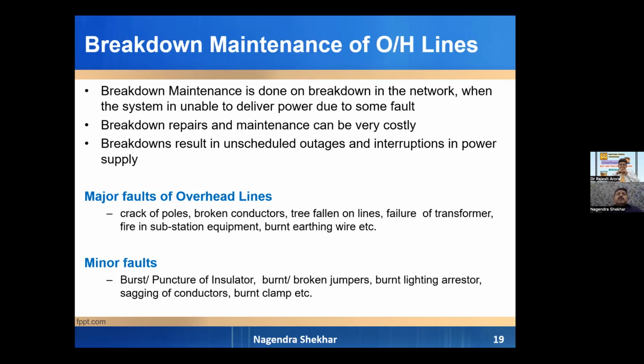Breakdown maintenance. Breakdown, as I told you, is when a system or network stops working, so we fail to deliver power supply to our consumers because of a fault. This fault can happen at any stage, because all equipment is connected in series, so a fault at any stage results in power failure in the area. When power fails, we have to find out where the fault has occurred and why, and we have to remove that fault. That may take some time. We have to backfeed the areas, then do the necessary breakdown maintenance. That is very costly and very irritating also.